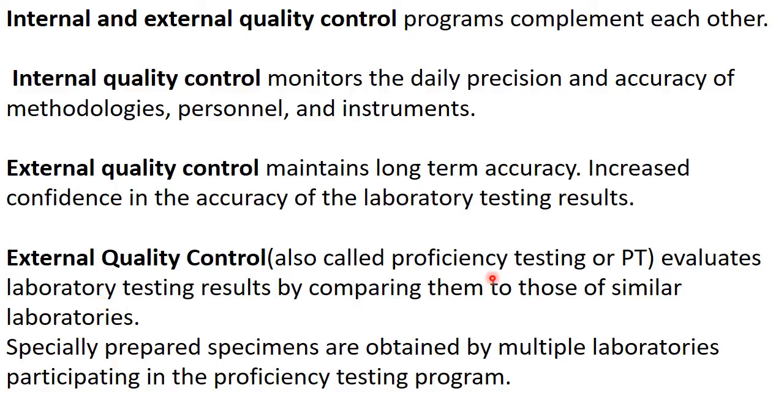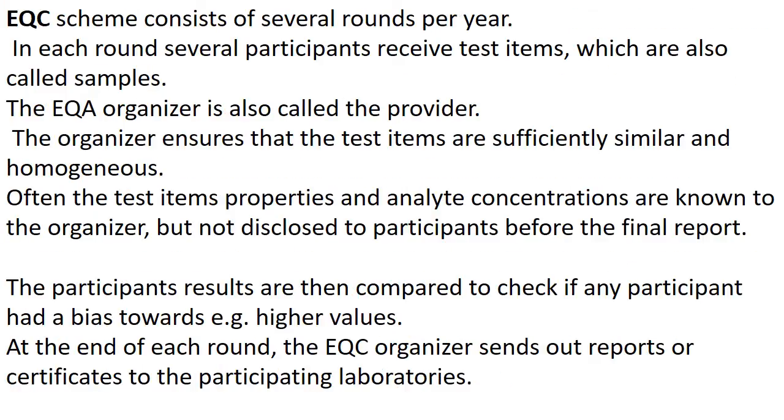Now external quality control. It is also called proficiency testing or PT. It evaluates laboratory testing results by comparing them to those of similar laboratories. Specially prepared specimens are obtained by multiple laboratories participating in the proficiency testing program. The external quality control scheme consists of several rounds per year. That is, in each round, several participants receive test items, which are also called samples.